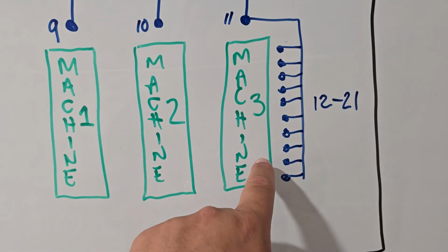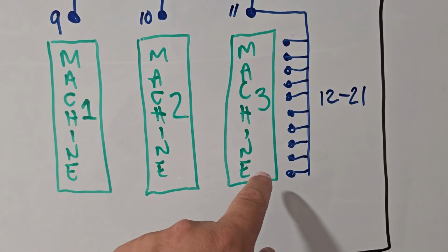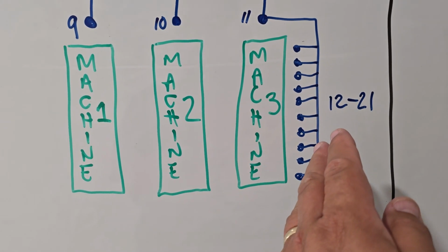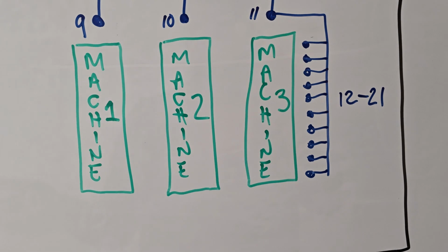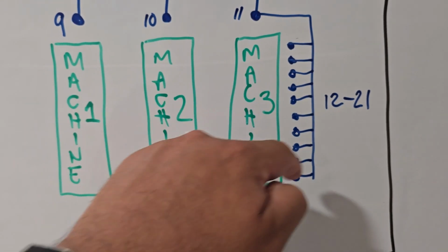So we have to create a boundary with the customer and say, is our boundary outside of this machine? Is that the limit to our system, or are we getting inside of it? Because if we get inside of it, now we're looking at tubing size increases, we're making sure the regulators are the right size, we're making sure the cylinders are correct, that we're actually using air correctly in here.